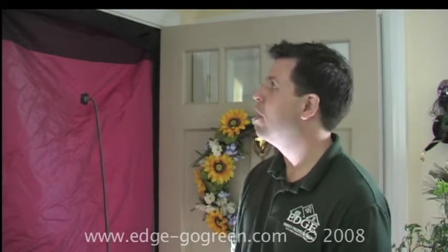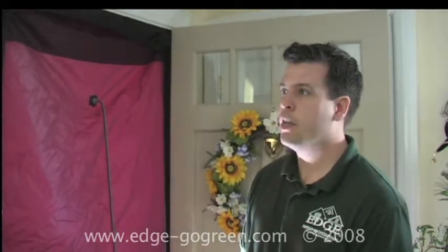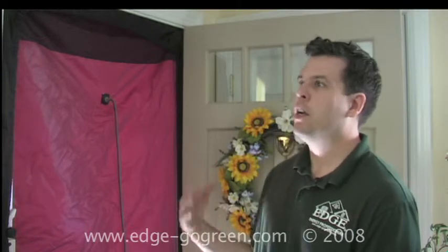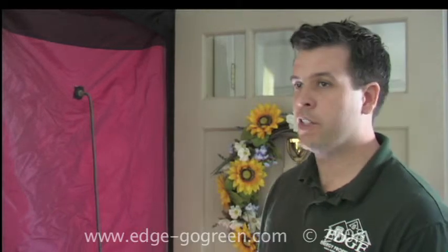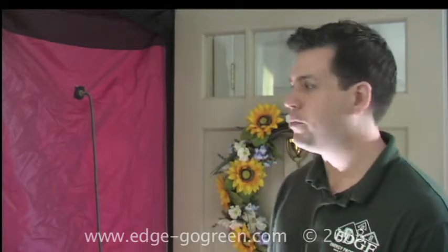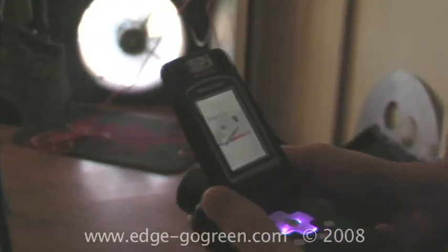So we just took 3 quick measurements with the blower door. Typically in an energy audit, we'll take 10 different pressure readings and then calculate back through logarithmic regression what the exact amount of building shell leakage is. And from that data, we can use a couple of other formulas to extrapolate out moisture control loads, how much air your house needs for minimum ventilation or suggested indoor air quality from ASHRAE, and uncover a couple of other issues possibly with the HVAC equipment that you're going to want to know about as far as depressurization or combustion safety issues.